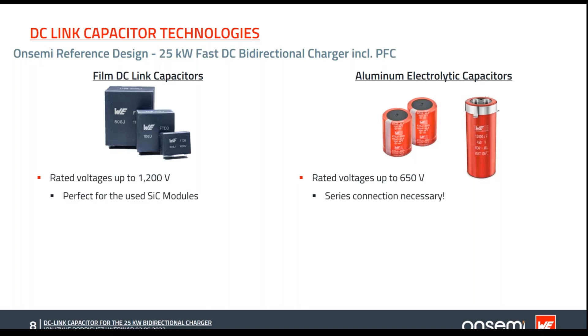Due to the very low ESR, polypropylene film capacitors can handle a very large ripple current, in comparison with the relatively high series resistance of electrolytic caps. On the other hand, for the same size, electrolytic capacitor cells provide many times higher capacitance in the same volume. So either you have capacitance or current capability. The consequence is that if we really need low ripple voltage on that DC bus, we might not get enough capacitance by adding film capacitors, so we might need to use electrolytic capacitors.